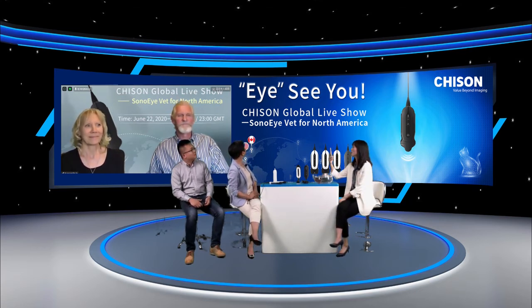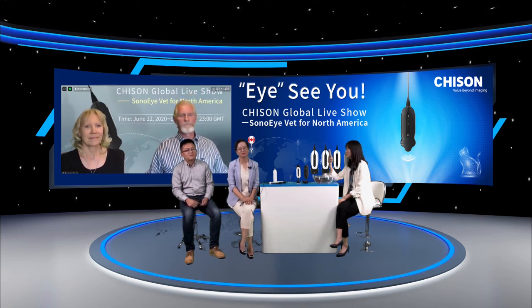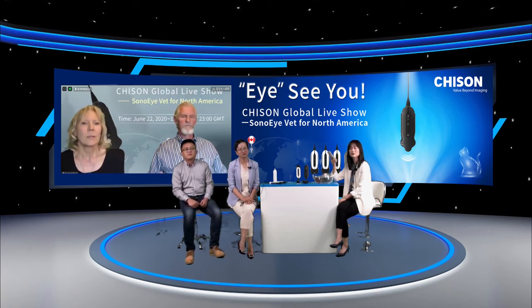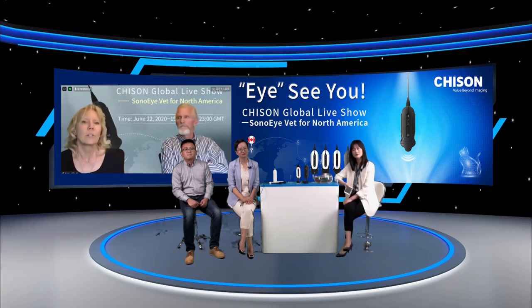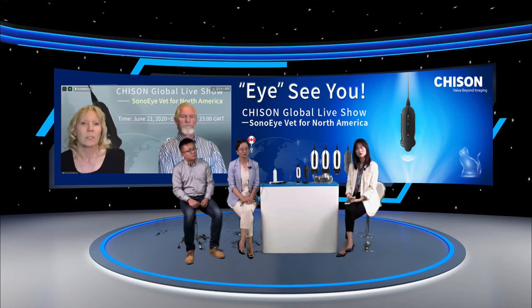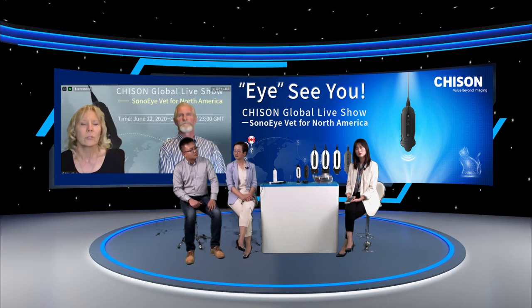The first question is, in which situation should we choose small convex, and in which situation should we choose linear for small animals? So in my opinion, I like to do the survey of the animal's abdomen with the microconvex to begin with. It has a wider field of view and I can see more. If I see something of interest, then I will get the linear transducer, as it has better image quality in my opinion, and it's easier to interrogate that structure with the linear transducer. So the linear transducer is for more superficial structures. The microconvex will allow for deeper imaging.